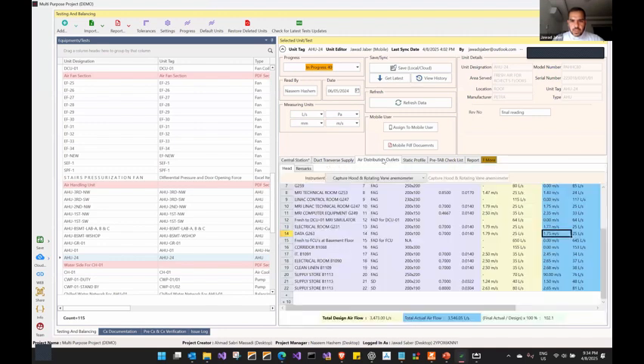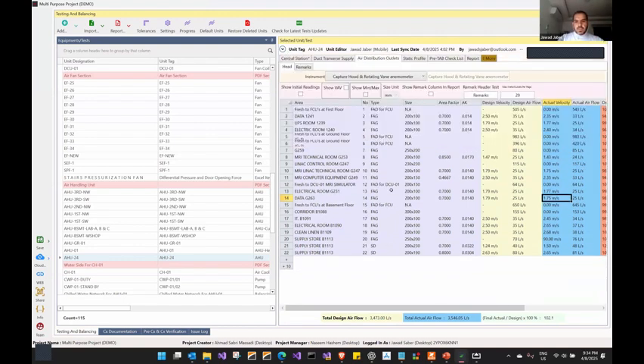Let's now dig into the air distribution. Here is the air distribution outlet. I can add one new outlet and call it supply diffuser, with dimensions 200 by 200, and I'll put 0.78 here - it calculates the AK automatically. If I put the design airflow, for example 75, it will calculate the design velocity based on this dimension.